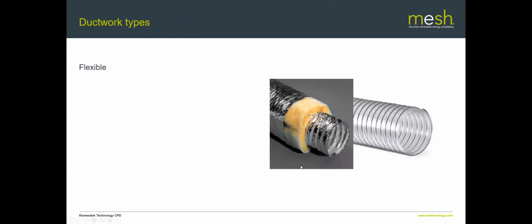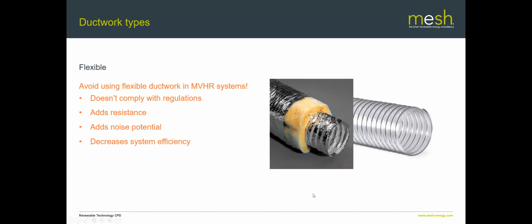And finally, we've got flexible ductwork, and flexible ductwork really should be avoided in most applications on MVHR. It doesn't comply with the regulations when used in long lengths. It does add resistance and it adds potential noise, and it's easy to crush. And obviously, if it was crushed, then it wouldn't allow the air that needs to go through it to go through. We've seen many installations where people have run flexible duct through loft spaces, and then householders ended up bashing it with a box while putting something in the loft, and lo and behold, their ventilation system doesn't work properly anymore.